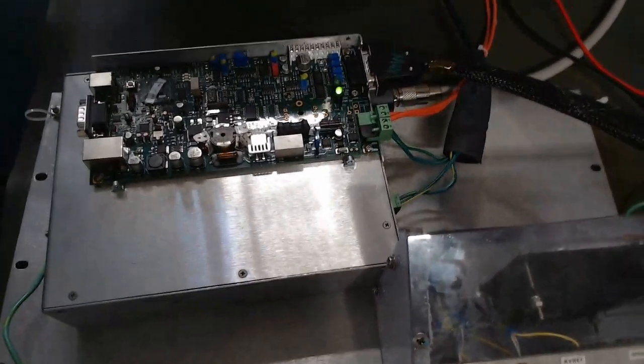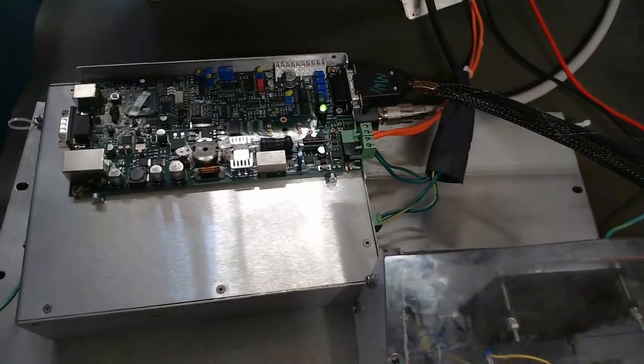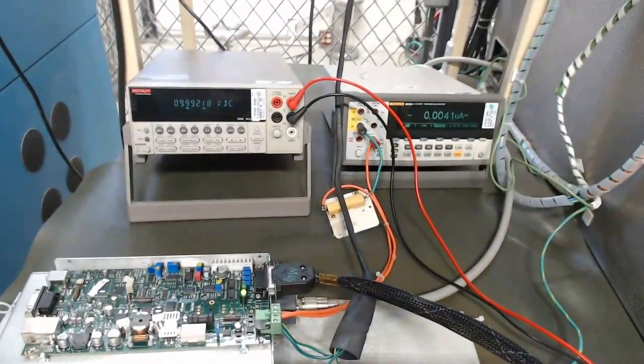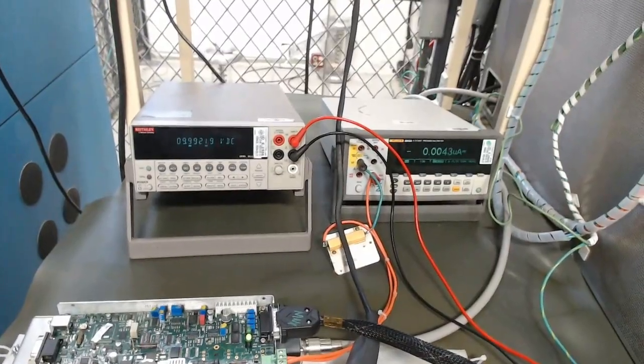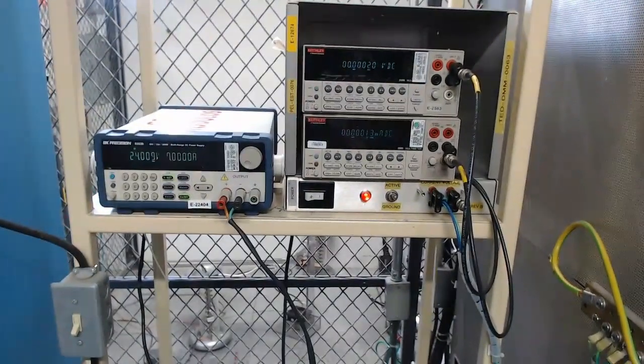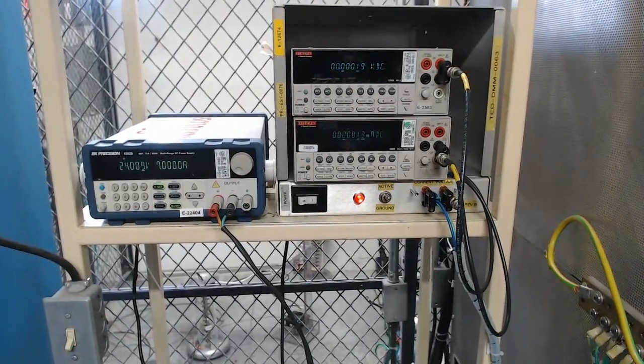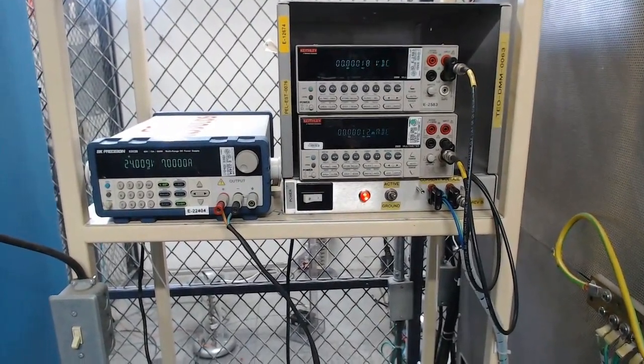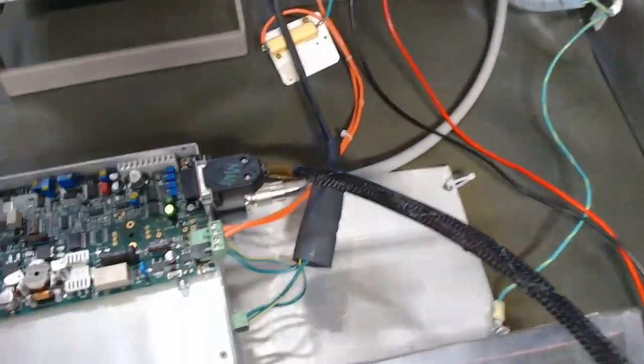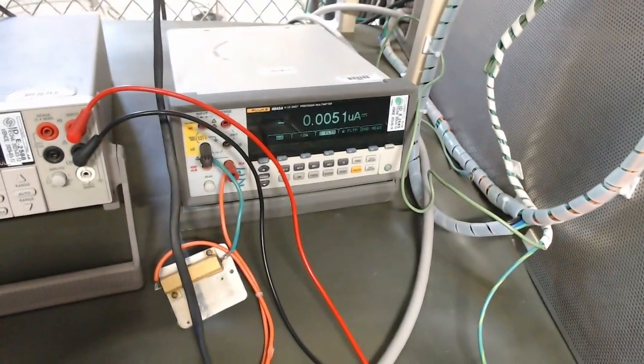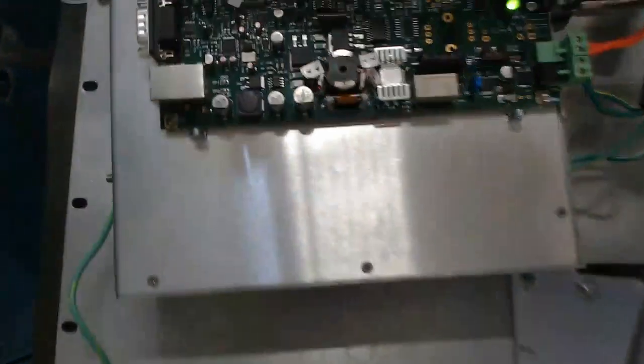calibration. Testing will begin with the output voltage and output current accuracy verification, where we will compare the output voltage and current to their respective programming and monitor signals. You should be able to tell from the image that the meter configuration is as outlined previously, with the output meters being in the same position. The filament output connected to the calibrated current meter through a 1 ohm load, and the test point meter to obtain test point data. It is important to remember that the configuration dip switch labeled as SW1 should be in the configuration shown to enable interaction through the analog interface instead of the computer interface.